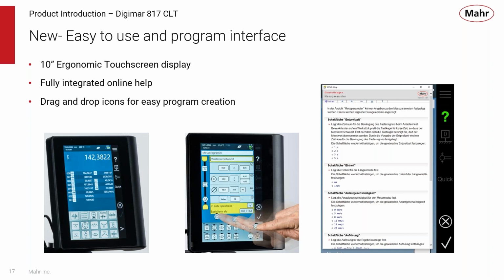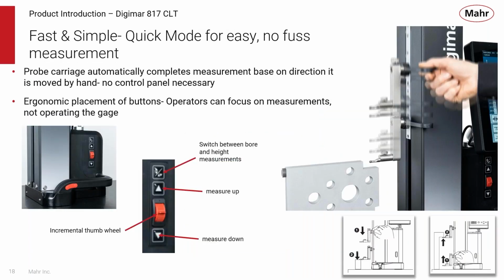The other feature that makes the 817 CLT so quick and painless to use is quick mode, made for easy pass/fail measurements. When quick mode is enabled, you can drive the probe carriage up or down, and the 817 will take over and continue driving it until it comes into contact with the part you're trying to measure, then give you a result. You also have the ability to use integrated touch buttons on the side of the 817.